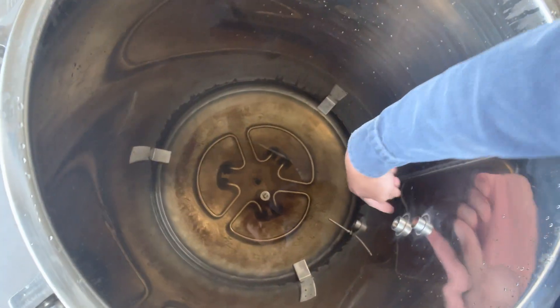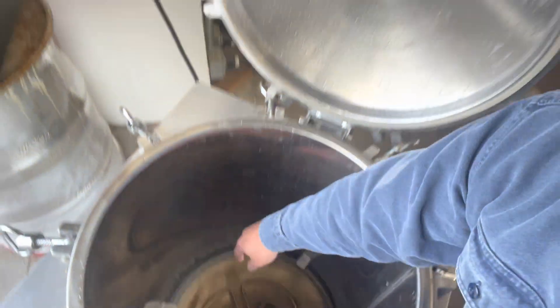Inside, as you can see, there's a heating element, gauges, and this cool float valve safety device. On the front panel there are two settings for water - either high or low. It needs to be at high in order to run. If it drops to low your run will cut off and stop, and it gives an error code. It doesn't use a ton of water - I go about an inch above the float valve. I can do two runs with that water level.